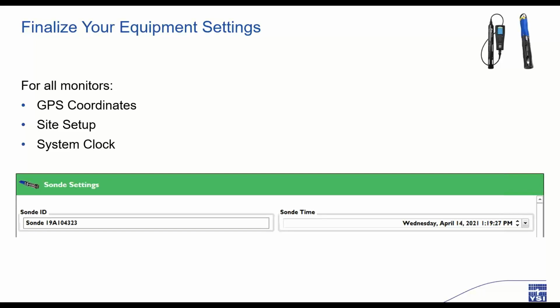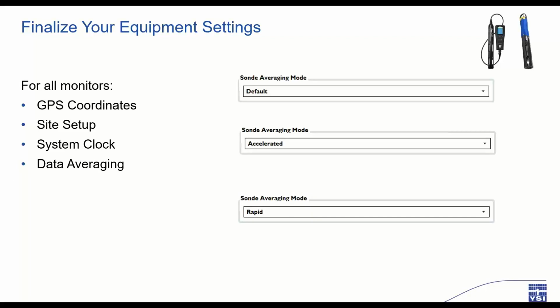In order to get an accurate timestamp, make sure to check the system clock on the handheld and your sonde. It is fairly common for people to forget to check the time in their equipment only to realize that all their data is tagged with the wrong times. Also, if you set an exact time for your sonde to begin logging data for deployment, it may not start when you want if the system clock is set incorrectly. I know the software actually has a function to sync the sonde clock with the PC time, so make sure you keep that in mind, and also make sure the handheld is consistent with the clock on the sonde.